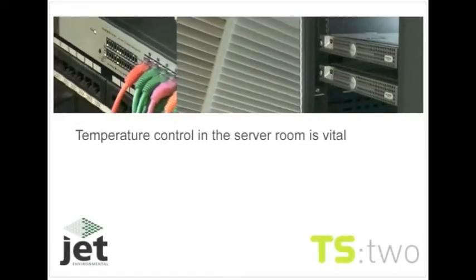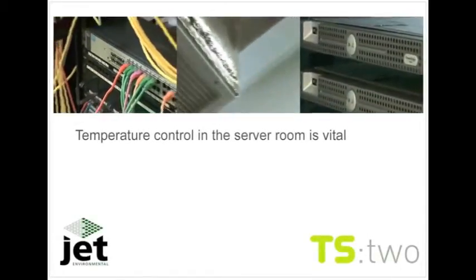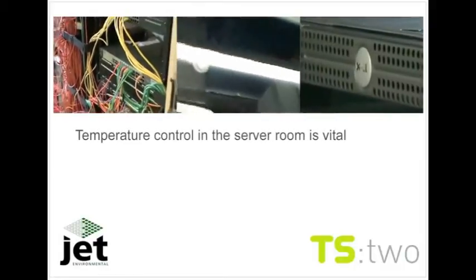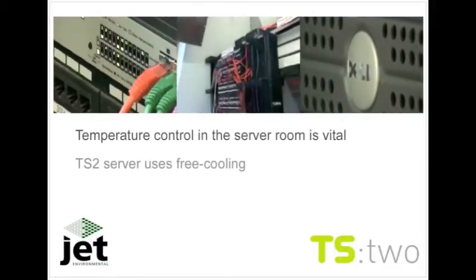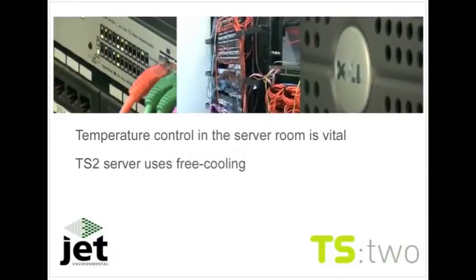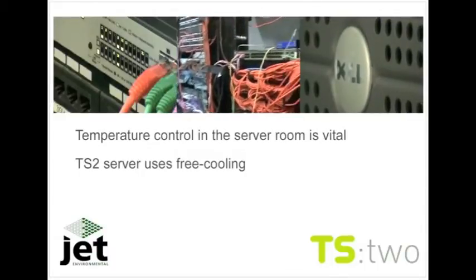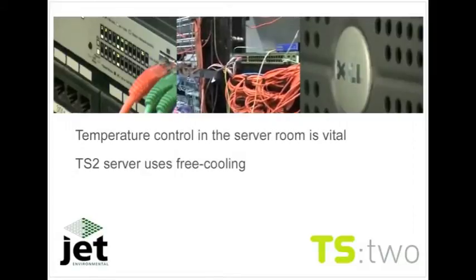Temperature control in the server room is vital to ensure optimal operating conditions and to protect the investment in IT systems. For TS2, a ducted system has been installed to maximise the availability of free cooling. The combination of variable airflow and recirculation allows the system to provide close temperature control all the time. The fresh air flow rate is then boosted to utilise free cooling when available. Only when conditions are not suitable will the system revert to mechanical cooling to meet demand. The energy saving is significant.